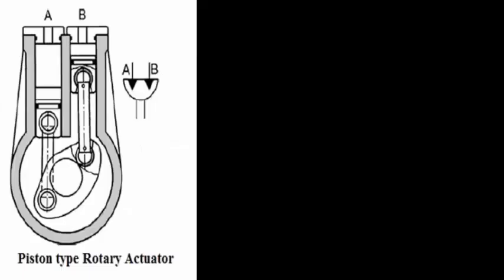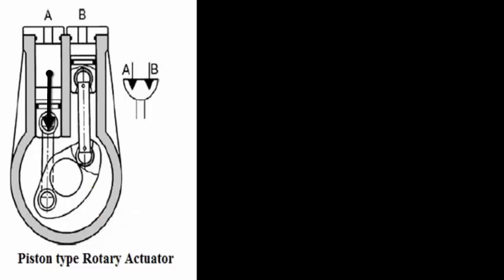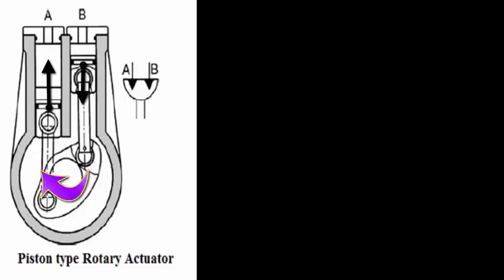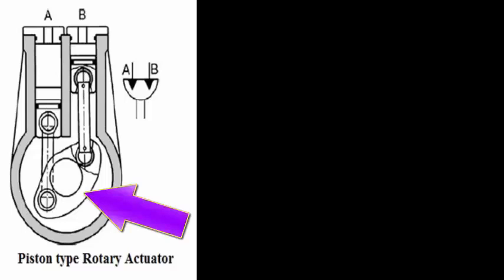That is about the vane motor configuration. Then you have the piston type rotary actuator. Here you have two pistons whose connecting rods are connected to a lever arm below. When you apply high pressure on piston A, the piston moves down and simultaneously piston B moves upwards, giving rotation at the center of the lever arm or crank. When you apply high pressure at B, piston B moves down and piston A moves upwards. By alternating the high pressure fluid supply to port A or port B, the corresponding pistons move upward or downward, achieving a twisting motion at the center of the crank. This is a simple method of achieving limited rotation using a piston and cylinder arrangement.